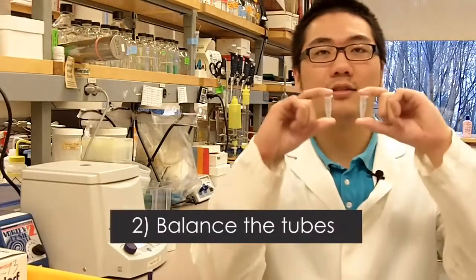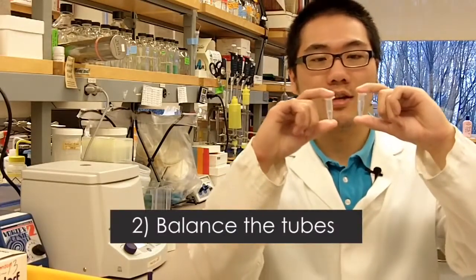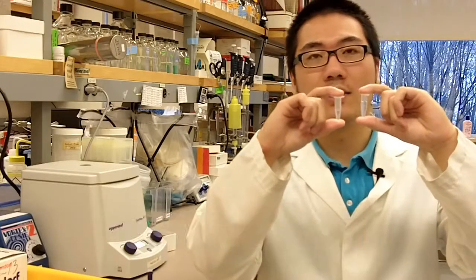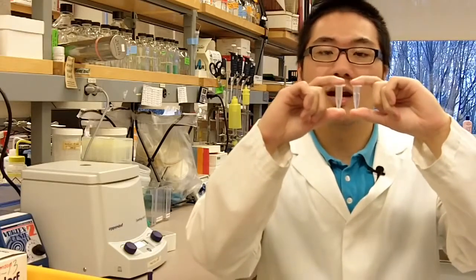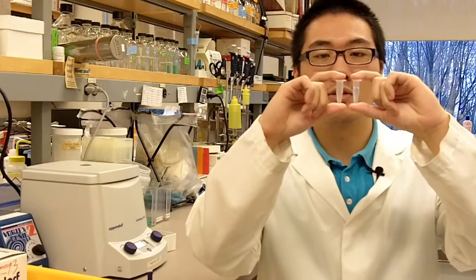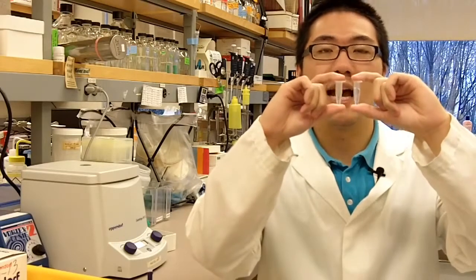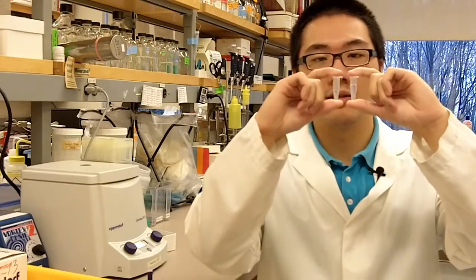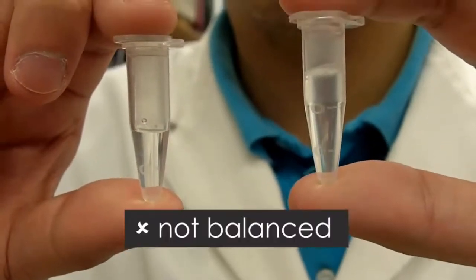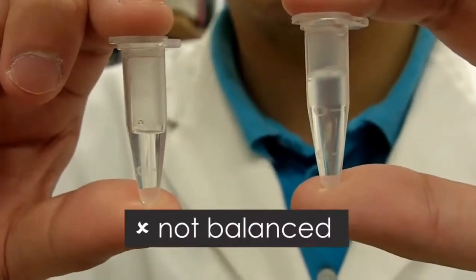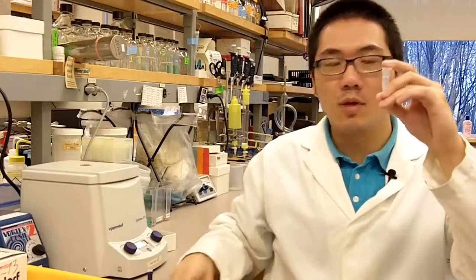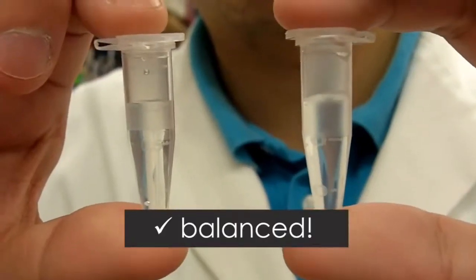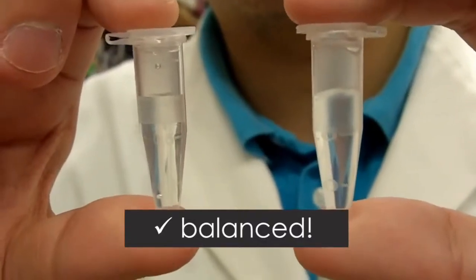The second thing you need to watch out for is you have to balance your tubes. So here, since the volumes you can put in the tube are small, you don't have to weigh them. All you have to do is make sure the solution in the two tubes is at the same level. As you can see now, the tubes are not balanced. One of them is at approximately 1 mil, the other one is at 0.5 mil. So in order to balance the 1 mil tube, you should have another tube which also has 1 mil of solution in it, like that.